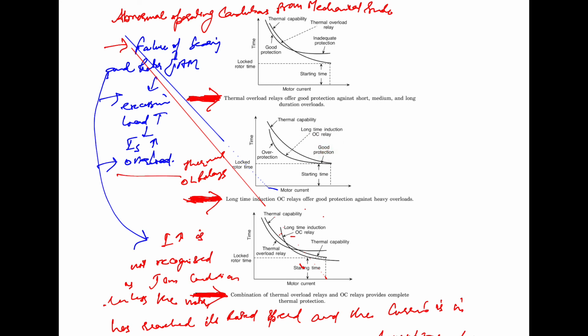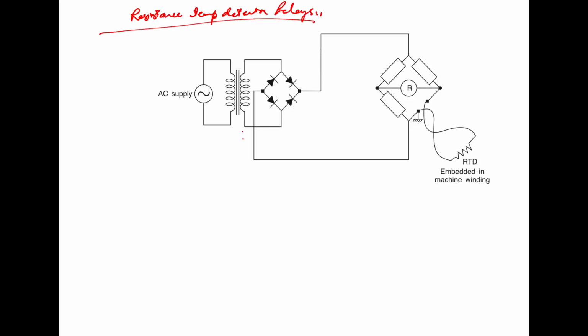However, if we use the combination of the long time induction overcurrent relay and thermal overcurrent relay, then it provides the complete thermal protection to the machine. In this way, this overload relay can be used for the protection. That is, we use the combination of both the relays to provide adequate protection. Another relay is the resistance temperature detector relay. These relays operate from one or more resistance temperature detectors that monitor the temperature of the machine winding, motor, load bearings or the load.